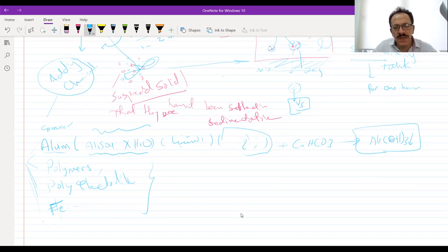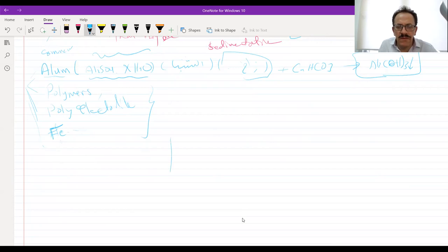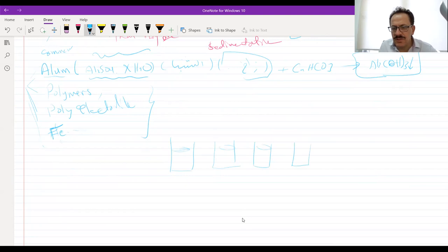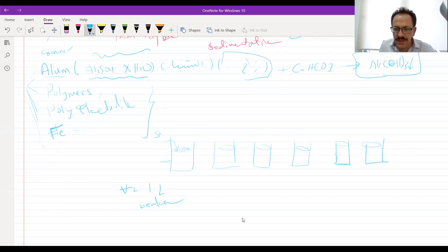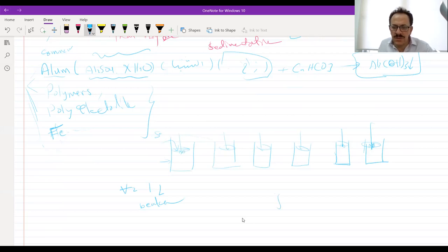How much alum should be added? Every day you should do a test called a jar test. The jar test uses six beakers, each with a volume of one liter standard. Samples of raw water are taken into these beakers. There will be mixers — there is a video showing how to do a jar test.